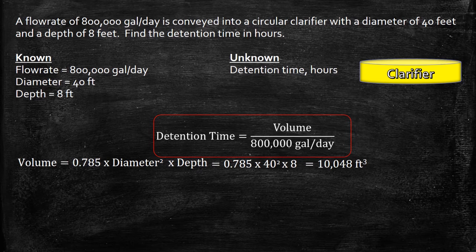The volume we just calculated is in cubic feet. We want the units to cancel out so we want to convert this cubic feet into gallons so that the gallons will cancel out and the detention time will be in days which we can convert later to hours.